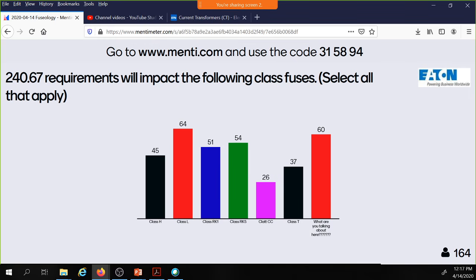The rest don't go up to 1200 amps and above. Your Class L, when you see a Class L fuse, that's the workhorse of your very large, 1200 amps and above type of installation. So I could tell we've got some learning to do with regard to the system.